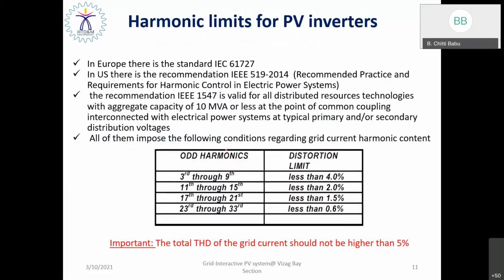Whatever be the control algorithm or control technique we impose on this inverter, still maintaining the grid current sinusoidal is a very difficult task, because 99% of the loads connected at the point of common coupling are electronic loads. Basically, they are highly non-linear loads. Due to the non-linear nature of the load, grid current is always non-sinusoidal. Obviously, it introduces lower order harmonics.